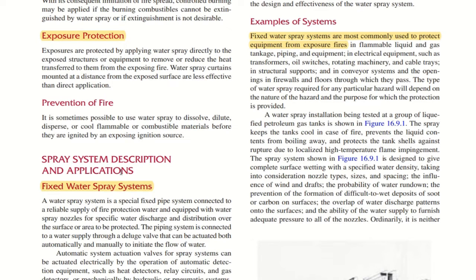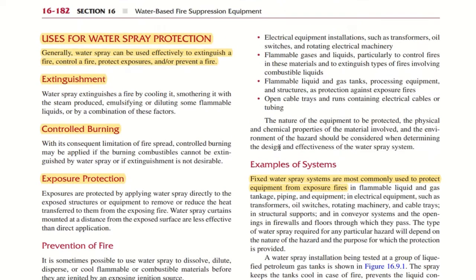Spray system description and application. Fixed water spray systems. Examples of fixed water spray systems. Fixed water spray systems are most commonly used to protect equipment from exposure, fires in flammable liquid and gas tankage, piping and equipment in electrical equipment such as transformers, oil switches, rotating machinery and cable trays, in structural supports, in conveyor systems, and the openings in firewalls and the floors through which they pass.